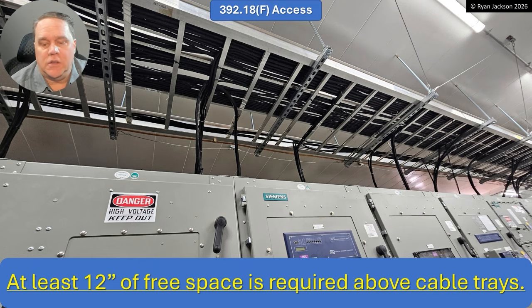Now it says you need at least 12 inches of free space above the cable tray. Cool. I don't know if 12 is the right or wrong number. It seems reasonable to me. I think with 12 inches, you could probably get up there and make a splice and see what you're doing and add wires. Probably ought to have more if you can get more, but sometimes it's not a perfect world. So you need at least 12 inches of free space above the cable tray.